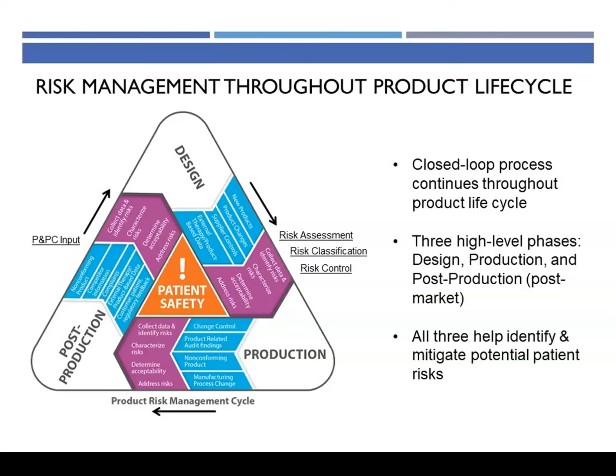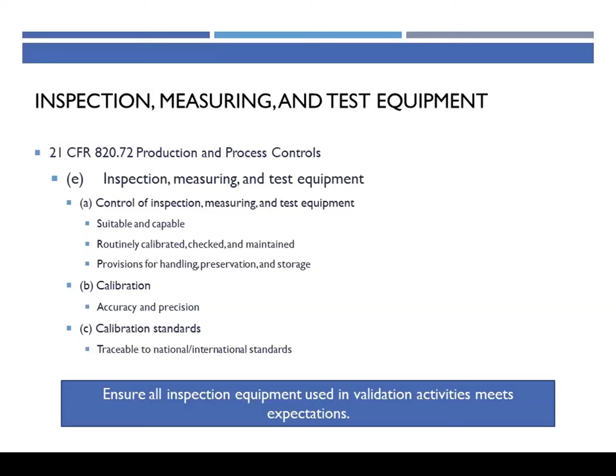Inspection, measuring, and test equipment for 21 CFR 820.72 is not explicitly validation, but we do see requirements that any inspection, measuring, or test equipment that you use during validation needs to meet these requirements. It needs to be suitable and capable. It needs to be routinely calibrated, checked, and maintained. You need to handle and store it properly. You need to calibrate it to known accuracy and precision standards. And it should be traceable to national or international standards. So any inspection equipment needs to meet this part of the regulation.